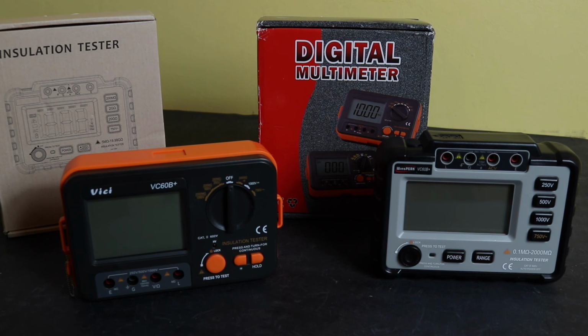Okay, so there you have it. A quick look at a couple of cheap insulation testers. Both VC 60B plus units, one from Vici, one from WinsPEAK. Would I use one of these professionally? I'd have to say no. For me, the output of the insulation test function doesn't meet the requirements of the IEC 61557-2 standard. Even if I tried to send this unit away for a calibration, it would probably come back as being failed.